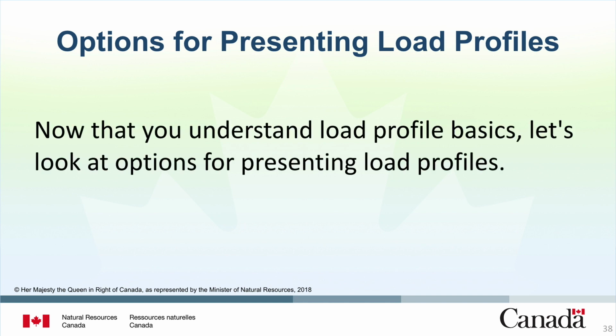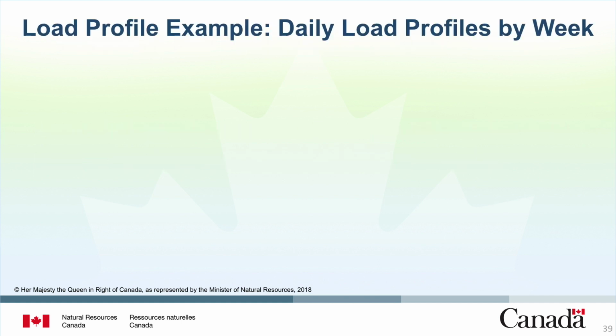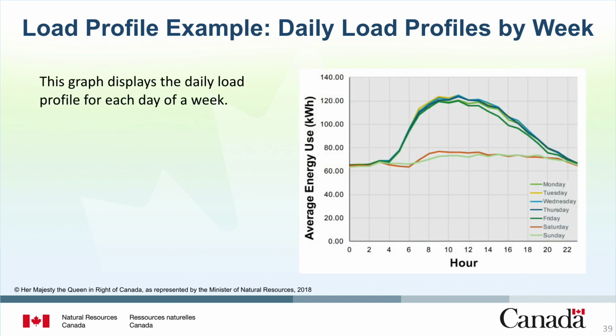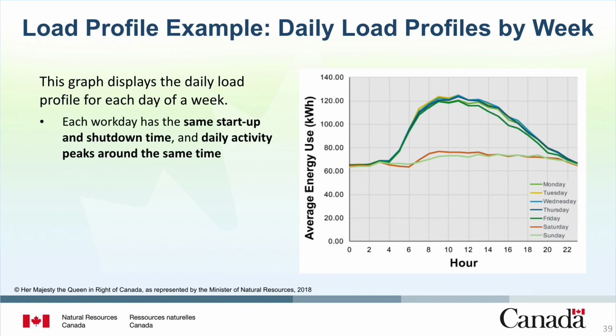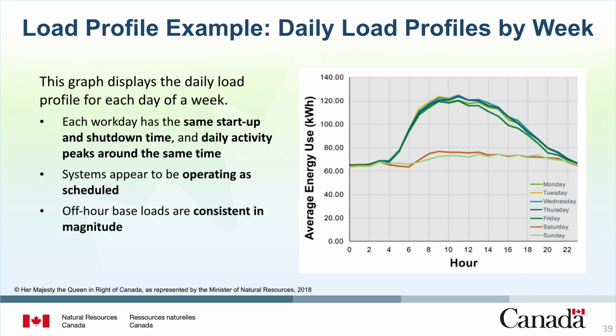Now that you understand load profile basics, let's look at options for presenting load profiles. Let's start with a daily load profile. This graph displays the daily load profile for each day of the week. Each workday has the same startup and shutdown time, and daily activity peaks around the same time. Systems appear to be operating as scheduled, and off-hour baseloads are consistent in magnitude.